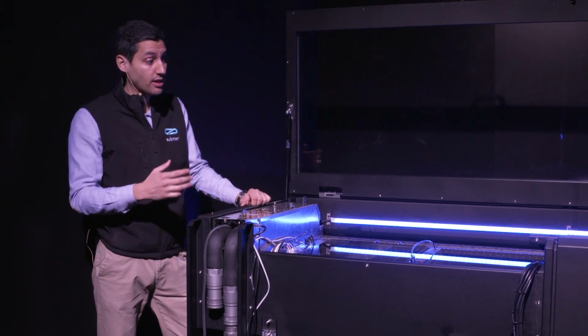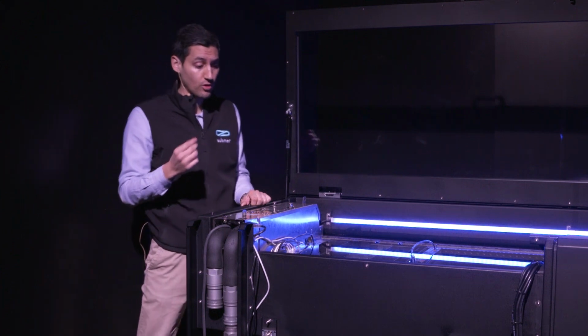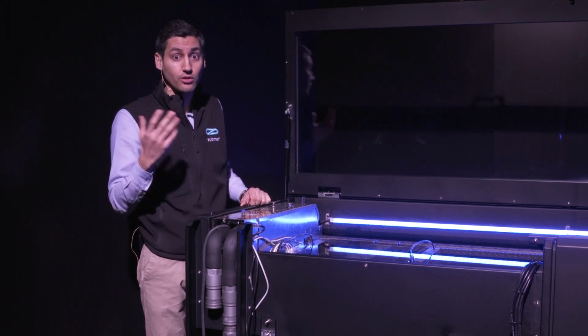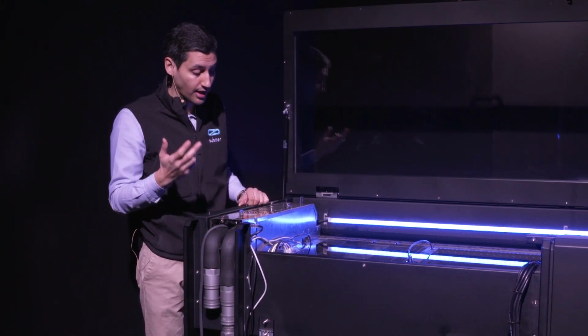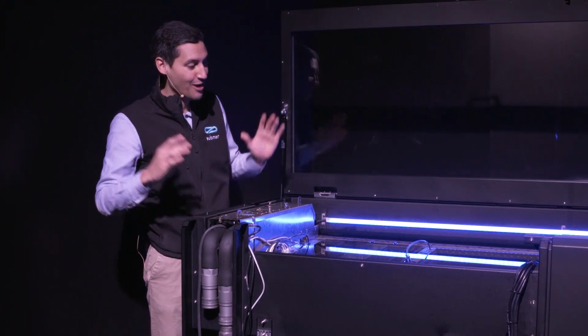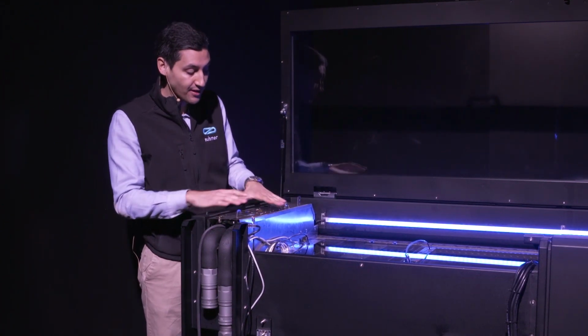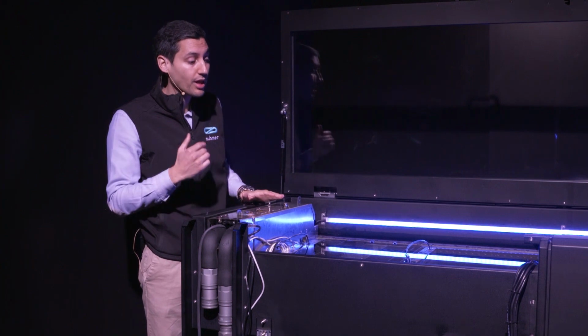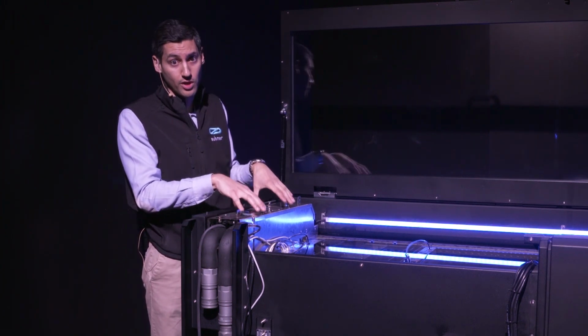Exactly, that's a very good question, and this is due to the thermal inertia. If you think about it, when you have a downtime in your air conditioning system in a traditional data center, you have 5 seconds, and everything goes down because of the heat. In this case, we have thermal inertia, so we have more than enough time to swap the CDU without downtime.